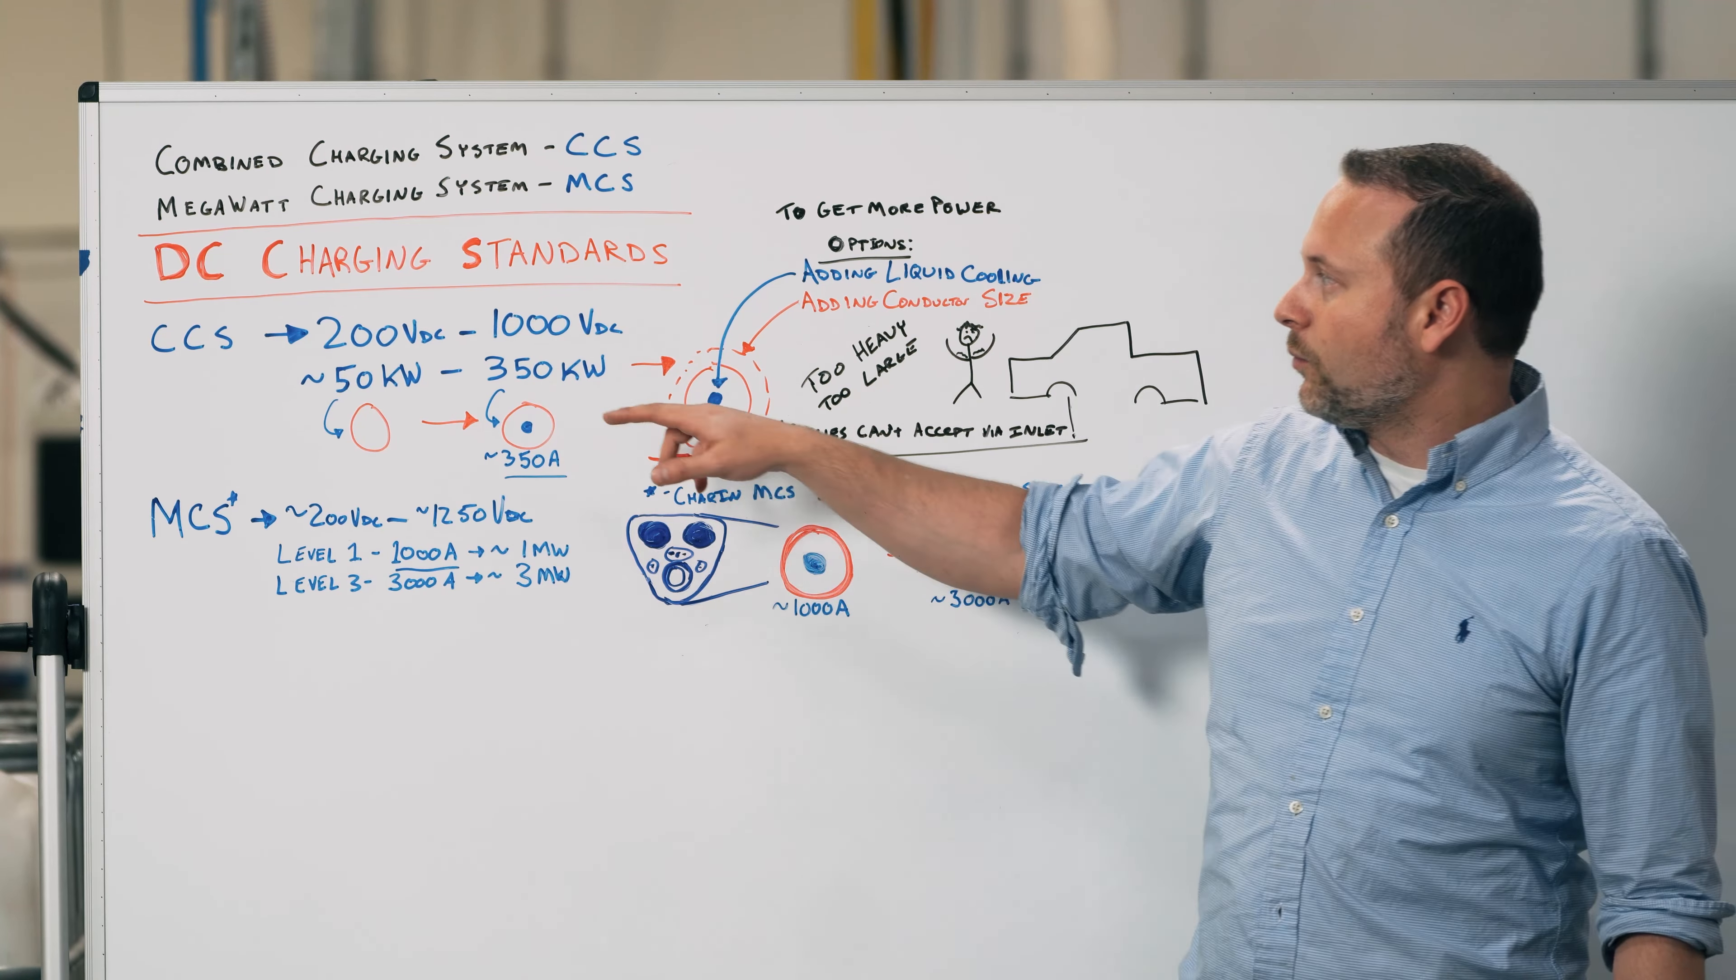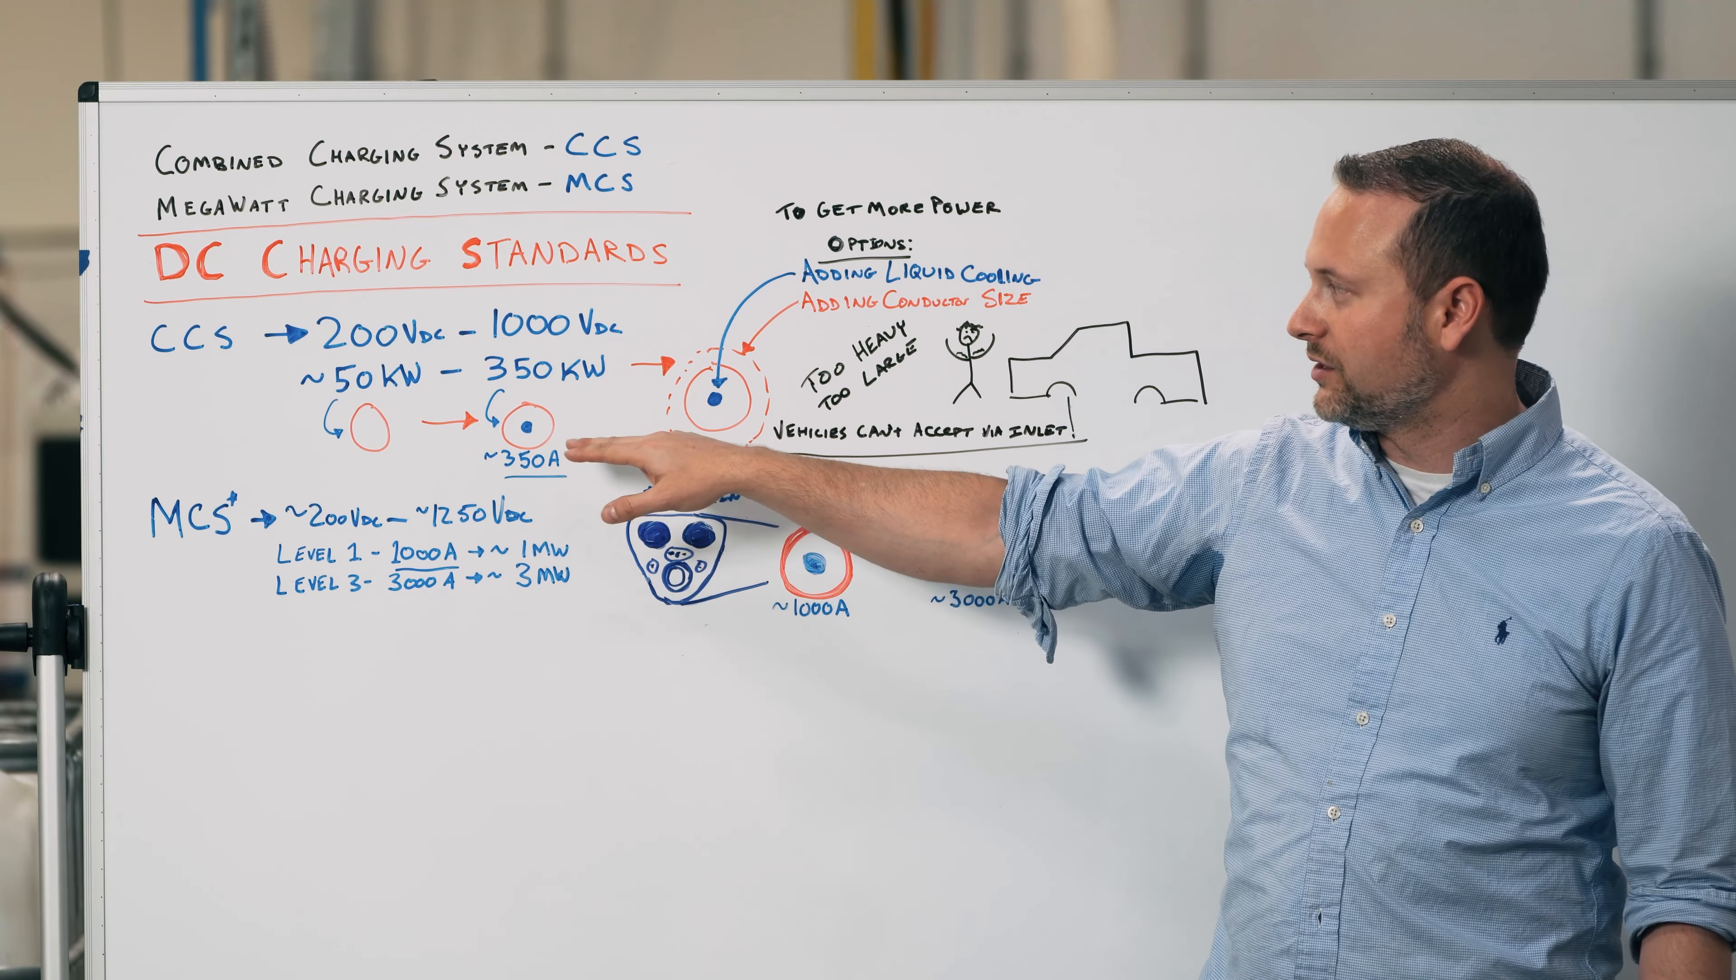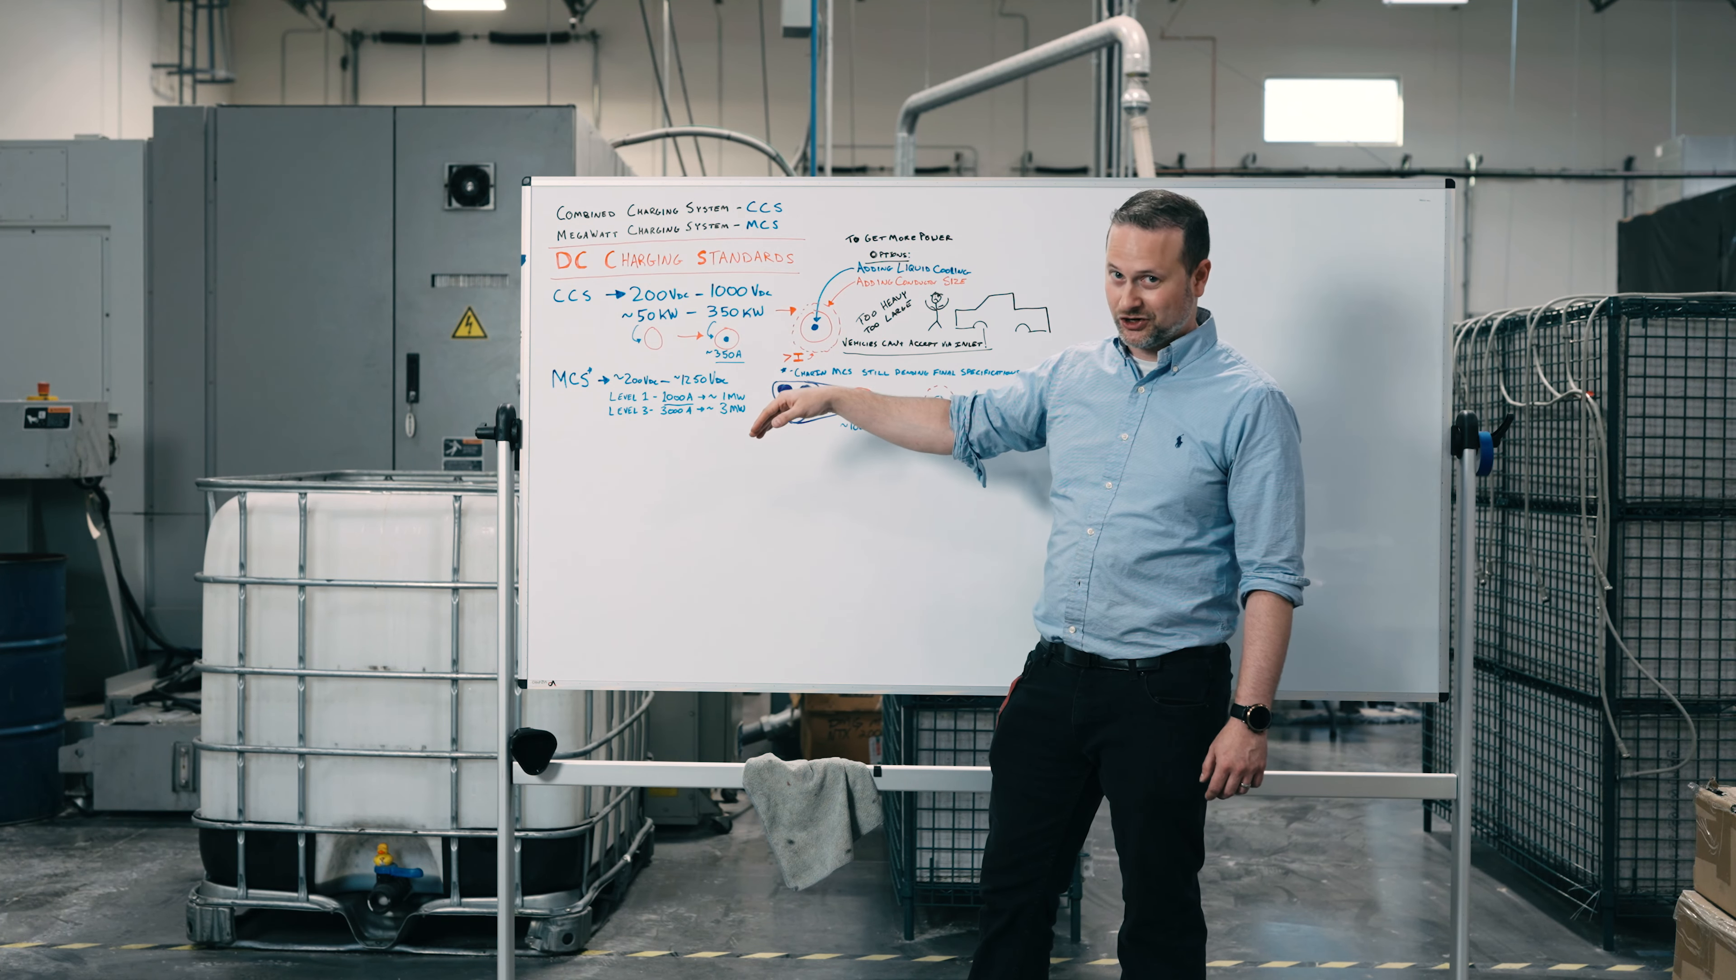When it comes to the higher power charging stations, you're going to notice that the conductor sizes are about the same size. But the way they achieve the higher currents through the conductor itself is by adding that liquid cooling. I wanted to clarify that for this video to talk about how we're going to achieve megawatt charging.